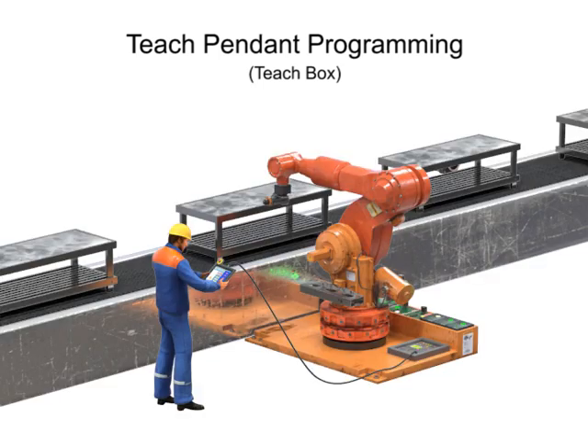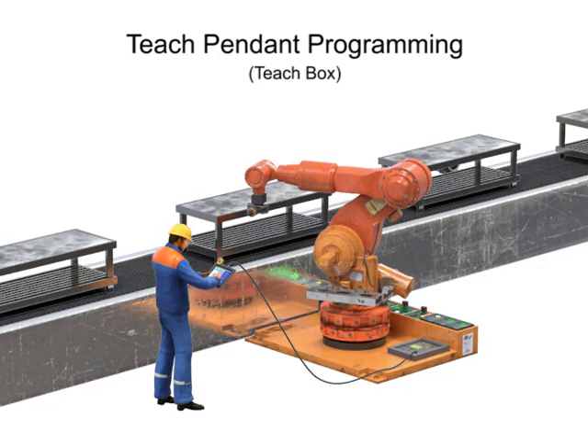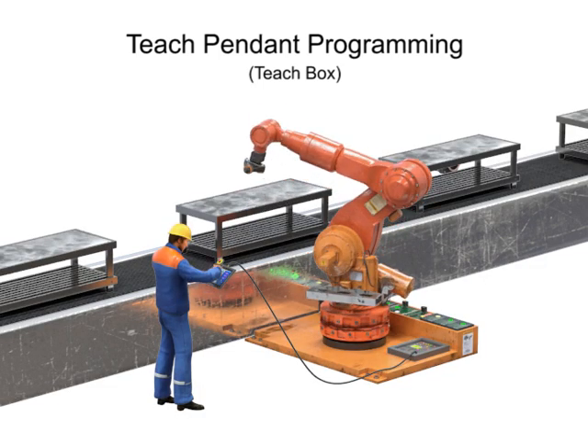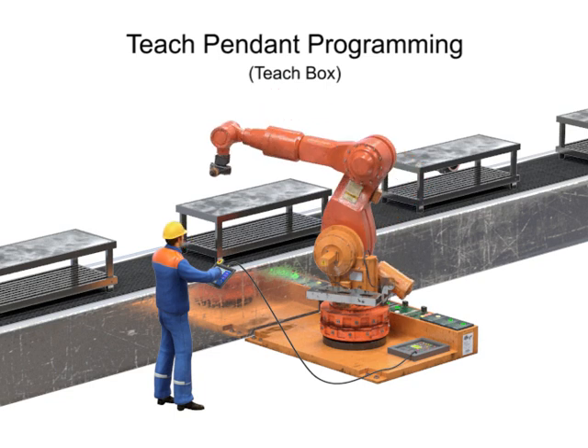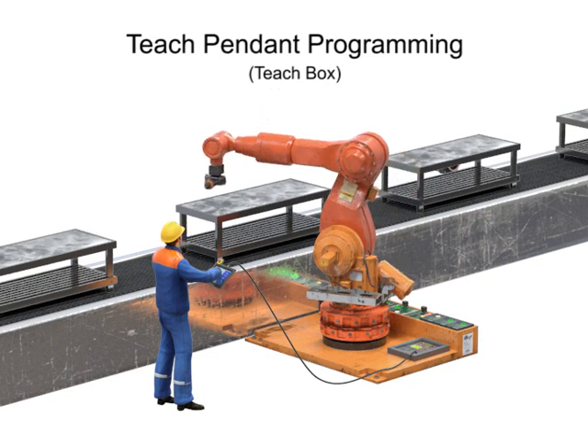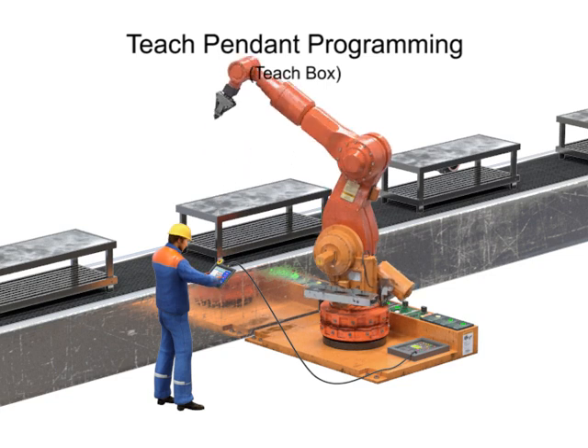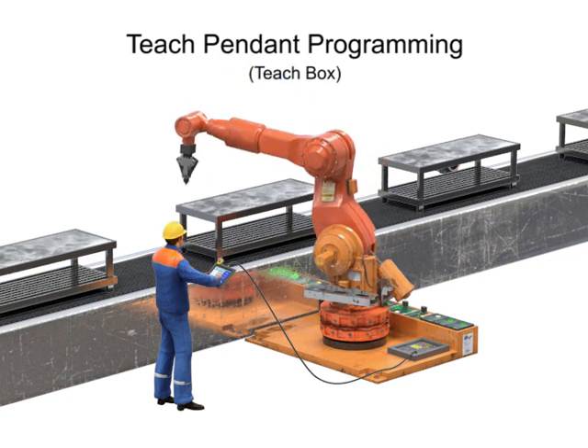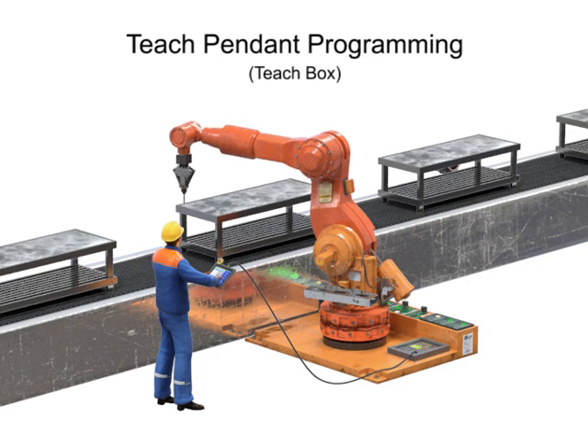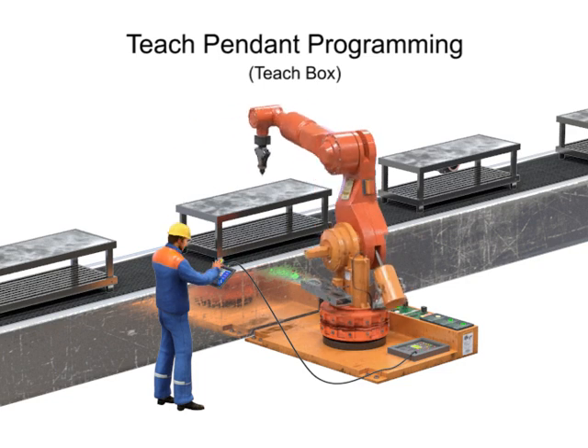Teach pendant programming is a method by which the operator steps the robot through the program point by point while recording the coordinates for each point. The technician has the ability to send the robot to a desired position, inch, or jog to adjust it and then record the point.